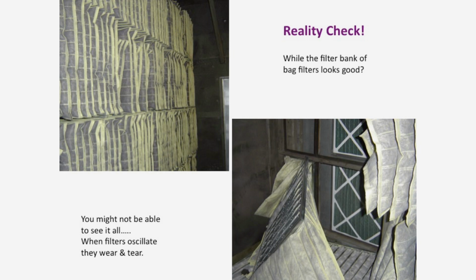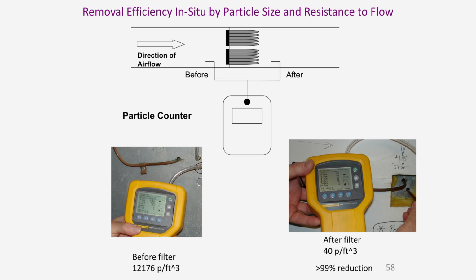So we certainly want our systems to run efficiently. We want them to run effectively by having filters properly installed, because that's the balance we want. We want to move air, but we want it to be filtered before it reaches our susceptible populations. And what I found, and this is not an approved method, is that by simply taking a particle counter, slide 58, and putting it across the filter bank, I can see huge differences.